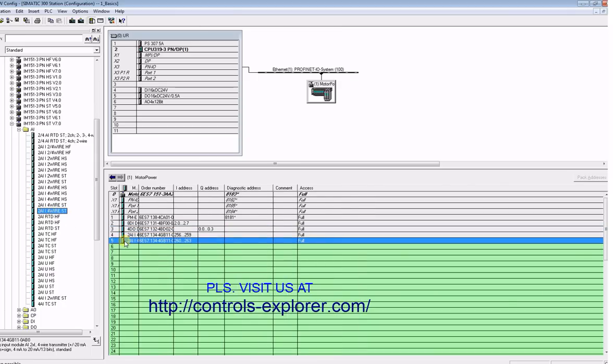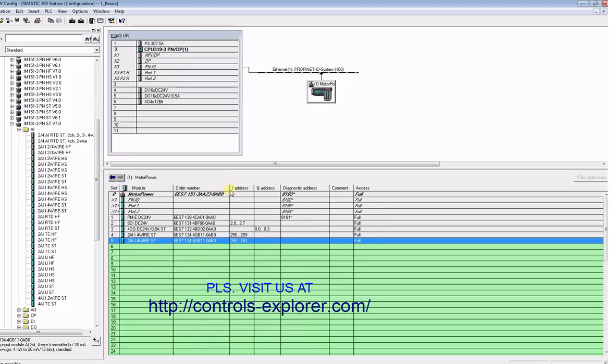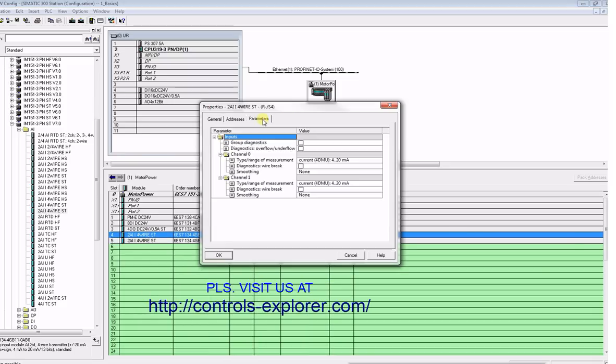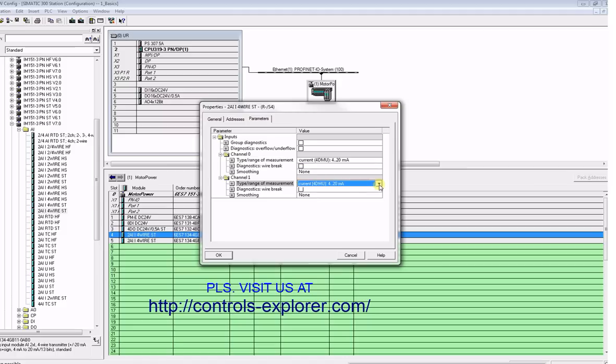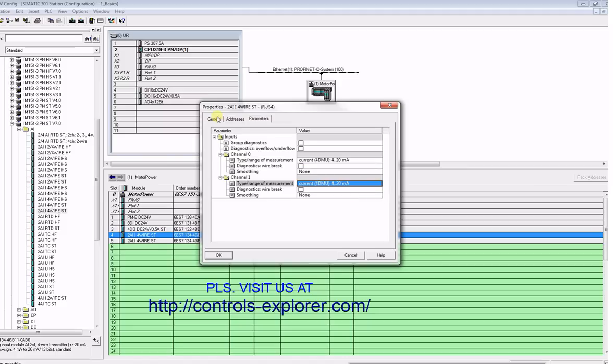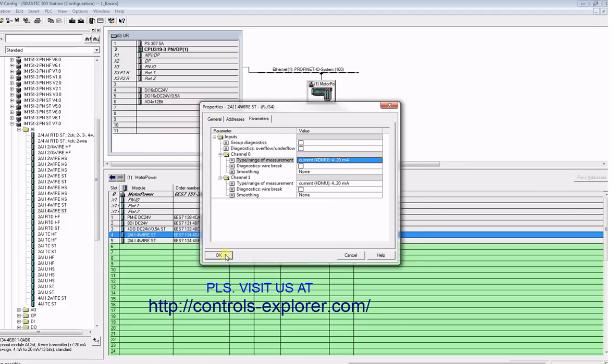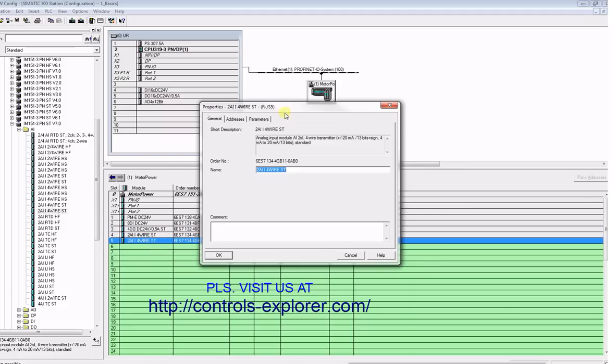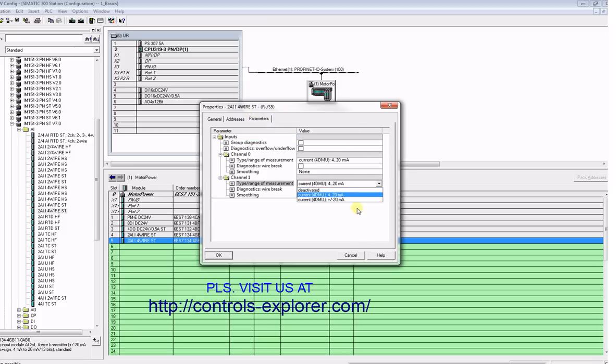Now drag and drop the analog input card, 2AI to slot number four and five. Save and compile. Double-click the analog input module, select parameters. Over here you could change it from 4 to 20 milliamperes or plus minus 20 milliamperes. For this example, let's keep it 4 to 20 milliamperes. Repeat the same process for the second analog input card.